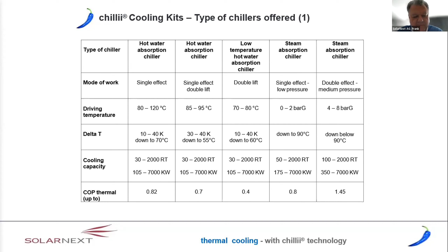Then you have a lot of other machines which I don't want to go through. Perhaps worth mentioning is the steam absorption chiller, with double effect meaning medium pressure, which has a higher driving energy because the temperature is about 160 to 180 degrees.